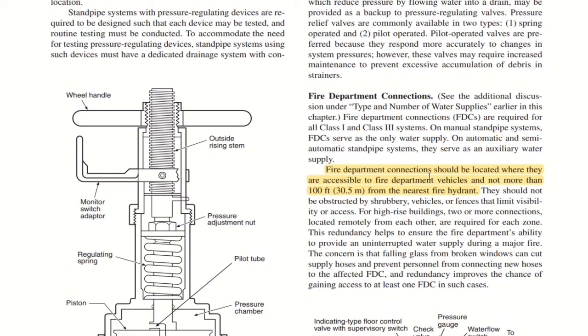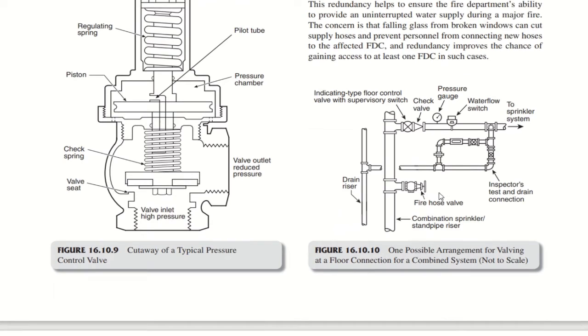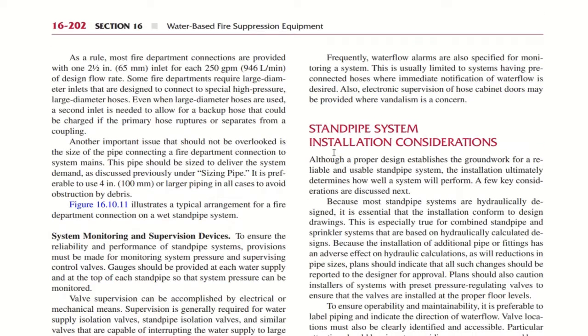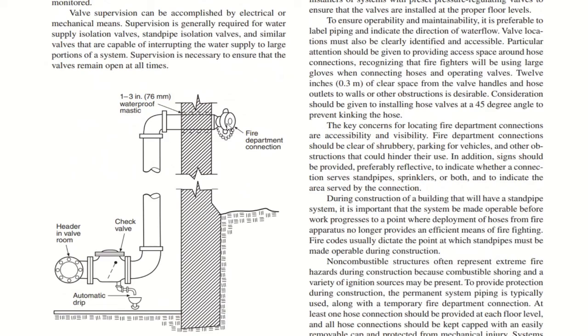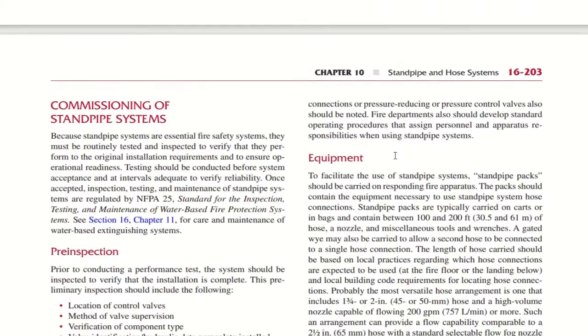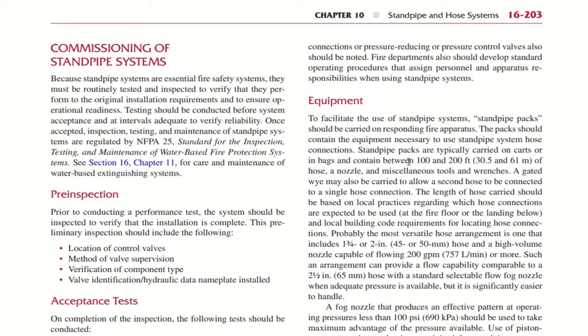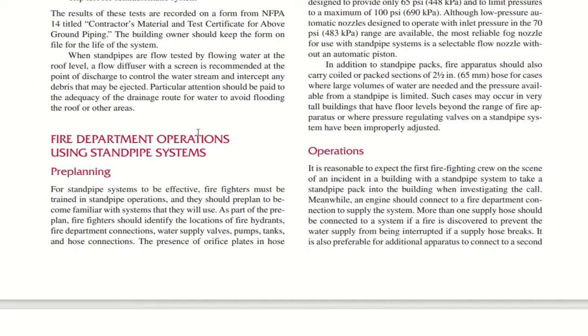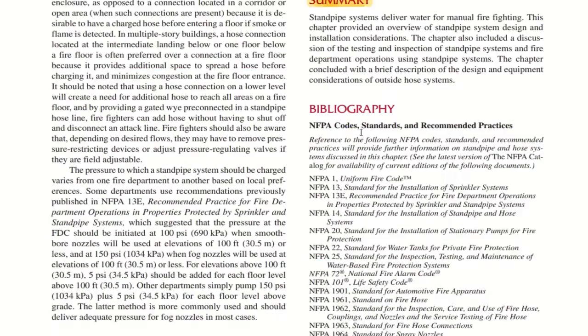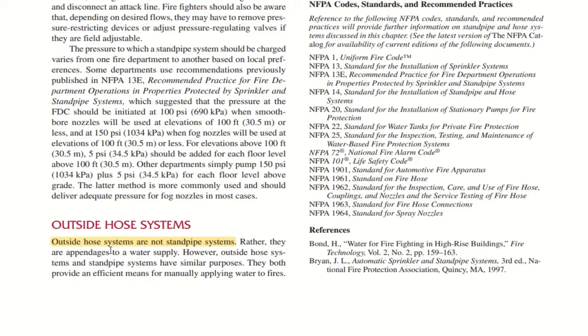So here you have the fire department connection. These are located where they are accessible to the fire department vehicles and not more than 30.5 meters from the nearest hydrant. So this is the small arrangement as per NFPA. You can see this riser consists of a fire hose valve and a zone control valve assembly as well. Standpipe system installation considerations. This is the fire department connection with a check valve. Commissioning of standpipe systems, pre-inspection and acceptance tests, and fire department operations using standpipe systems, pre-planning, equipment operations, and so on. So basically this covers the hose systems and standpipe systems.